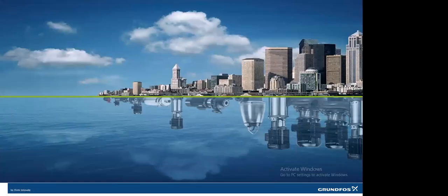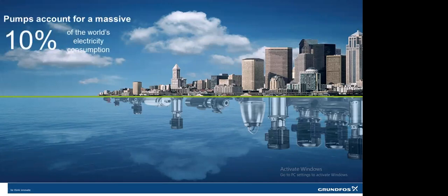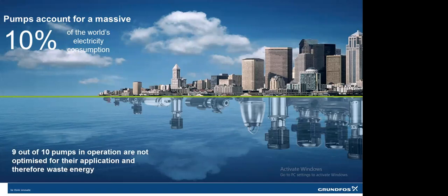Speaking about pumps, they are used for every application. If we are in industry, pumps are required for all the utility purposes: HVAC systems, cooling tower systems, process pumps, or process cooling as well. And in commercial buildings, they are required for HVAC as well as water treatment plants and dewatering systems. Based on data collected from global organizations, 10% of the world's electricity consumption is consumed by pumps, and 9 out of 10 pumps in operation are not optimized for their application and therefore waste energy. So more or less 80 to 90% of pumps are eligible for energy saving by modification in the pump or in the system. How to achieve that, we'll discuss one by one.